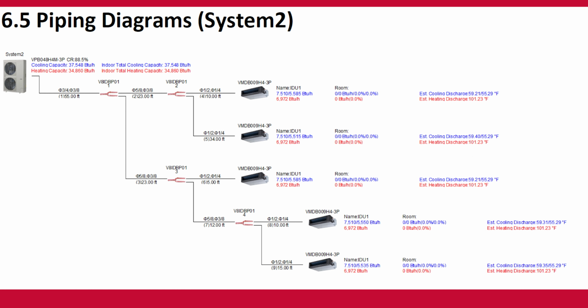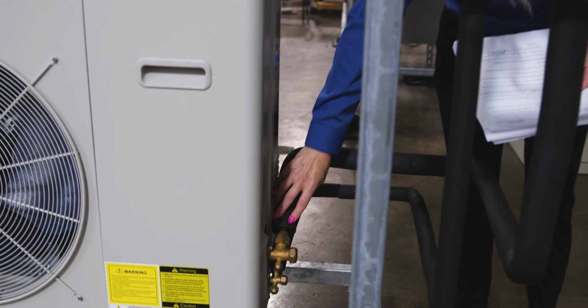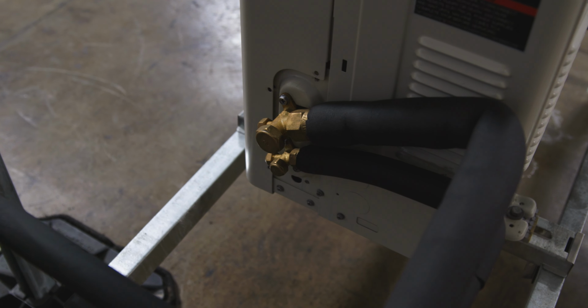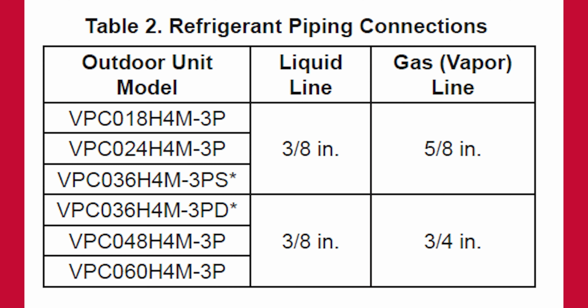The connections at the outdoor unit are flared. The connection sizes depend on the unit size. The single fan cabinets have a 3/8-inch liquid pipe connection and a 5/8-inch vapor line connection. The dual fan cabinet models have a 3/8-inch liquid pipe connection and a 3/4-inch vapor pipe connection.